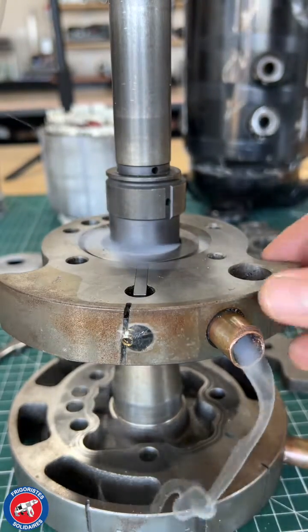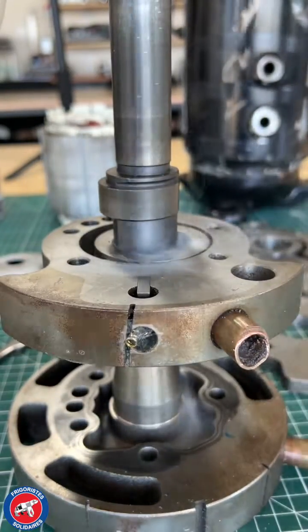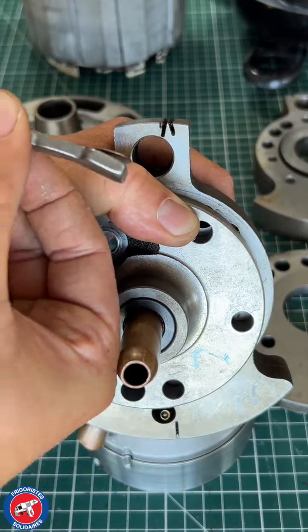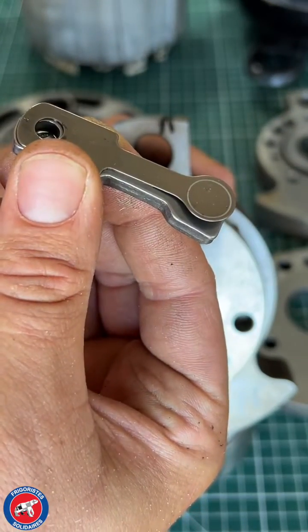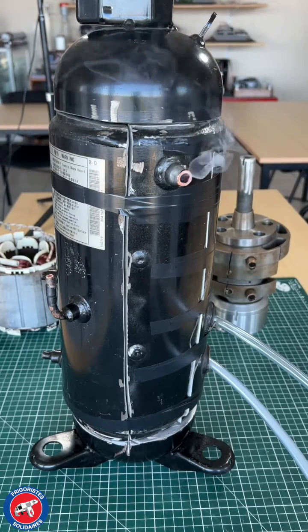The first stage is located in the lower part of the compressor. Its suction is in direct communication with the low pressure piping. The discharge valve is orientated towards the bottom of the crankcase. The compressor shell acts as an intermediate oil separator.